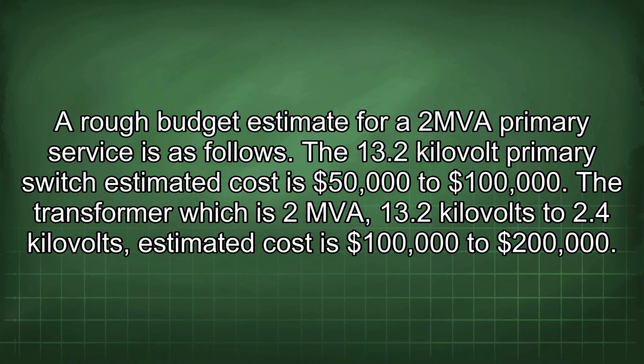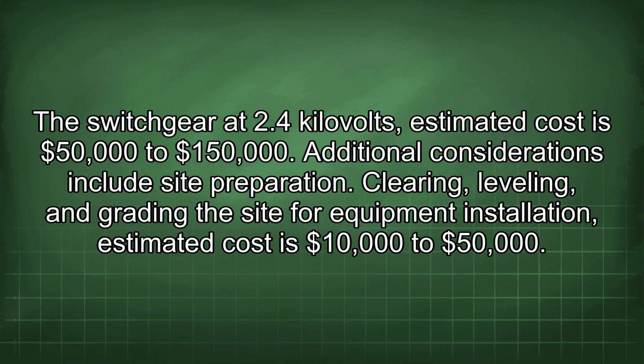A rough budget estimate for a 2 MVA primary service is as follows. The 13.2 kilovolt primary switch estimated cost is $50,000 to $100,000. The transformer, which is 2 MVA, 13.2 kilovolts to 2.4 kilovolts, estimated cost is $100,000 to $200,000. The switchgear at 2.4 kilovolts, estimated cost is $50,000 to $150,000.